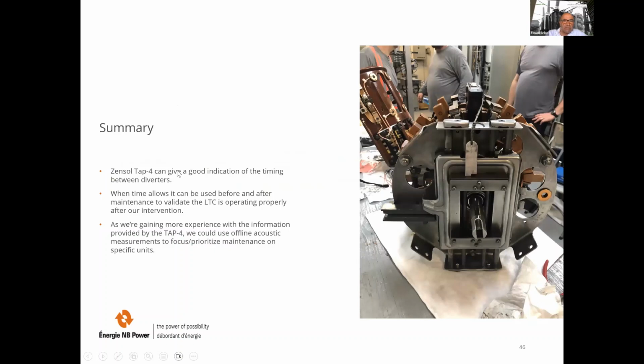So Zensol Tap 4 can give a good indication of the timing between diverters. When time allows it, it can be used before and after maintenance to validate the LTC is operating properly after our intervention. As we're gaining more experience with the information provided by the Tap 4, we could use offline acoustic measurement to prioritize maintenance on specific units.